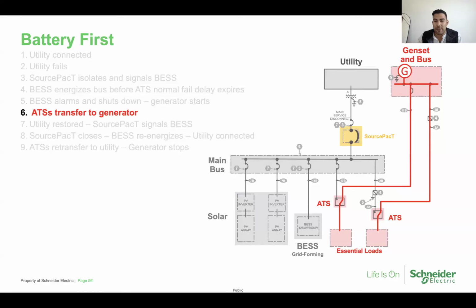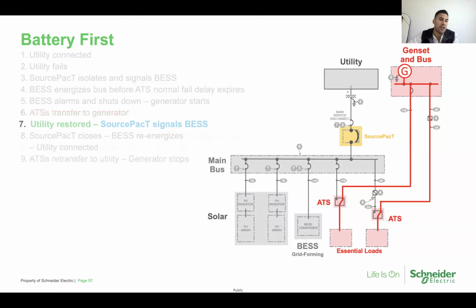This could be like an inclement weather condition where they lost power. Anywhere where you have a situation where you completely depleted the reserve of the battery energy storage system, you're calling on your diesel genset. And this is that N+1 redundancy that we're calling on here, where you have the battery first scenario, where you depleted the reserve, and then calling on that generator for that secondary power source.